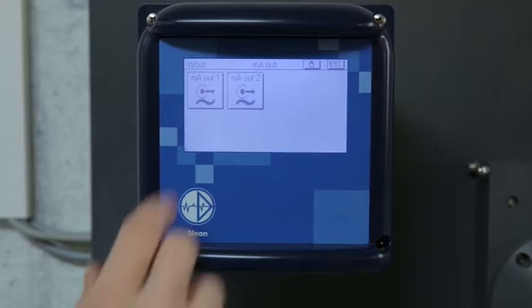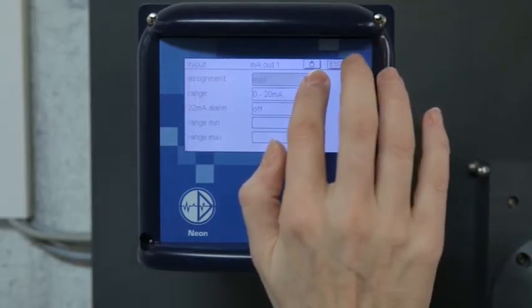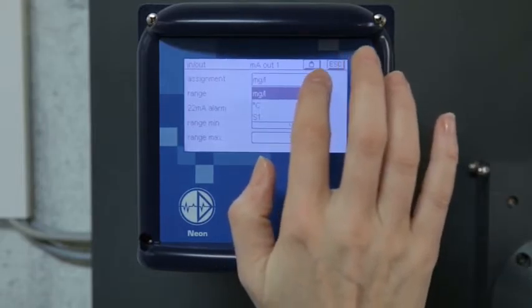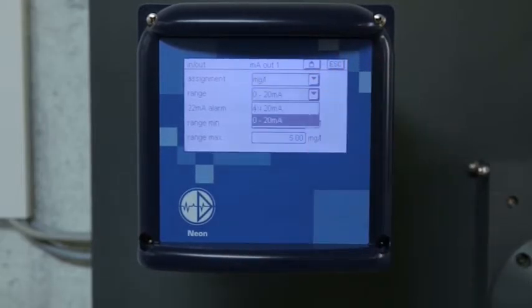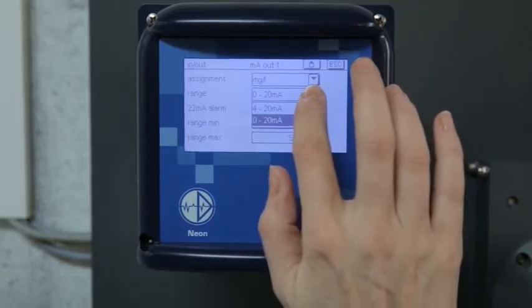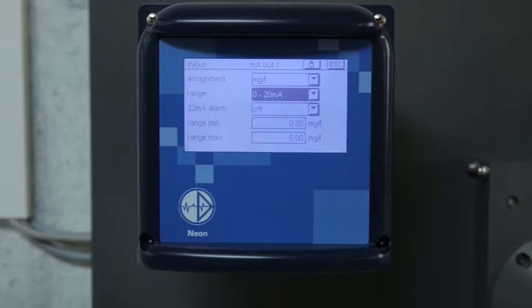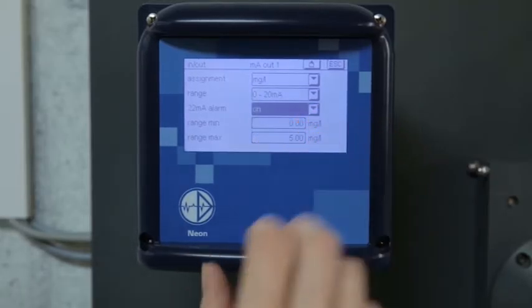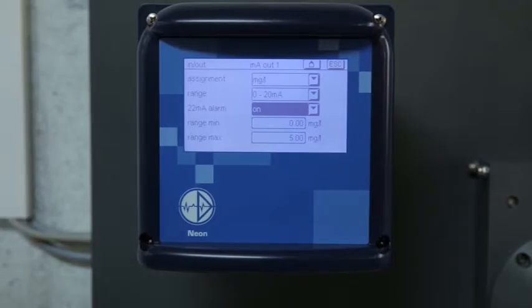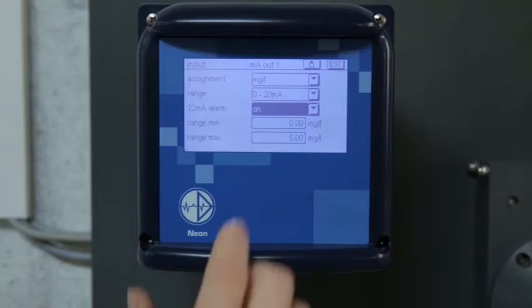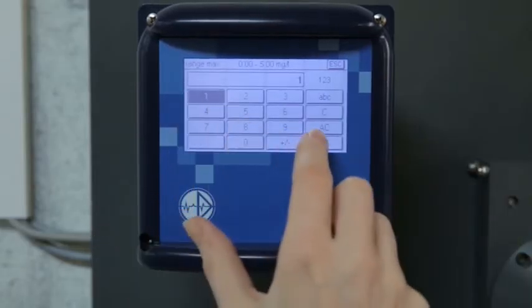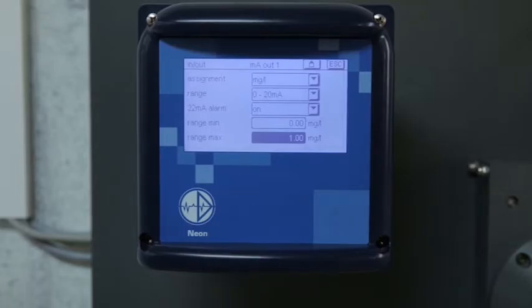We connected 1 mA output that may be used as readout for measured value, temperature value, or control variable. You can choose whether you want to set the output range to 0 to 20 or 4 to 20 mA, and whether you want a 22 mA alarm to go off in case of faulty measurement information. The milliampere output can be scaled if you're interested in just a certain section of the measuring range, for example 0 to 1 milligram per liter. The minimum value always corresponds to the minimum milliampere value, in this case 0 milliampere. The maximum value corresponds to 20 milliampere.